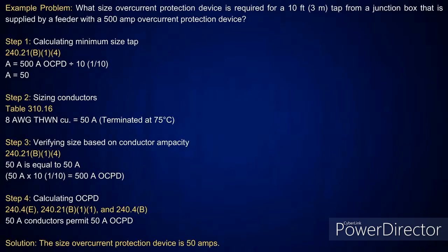Now, here's one. I'm doing a tap. Okay? So I'm going to ask you what size overcurrent device is required for a 10-foot tap from a junction box that is supplied by a feeder with a 500 amp overcurrent device that's upstream. I'm going to go 10%. Everybody remember what I've said on this. When you're doing taps, anything 10 foot or less, I divide by 10. Anything over that 10 foot, you take at a third. And if I did a tap with a transformer in the tap, you still do the primary at a third, but the secondary, you have to do it at a third with the ratio of the transformer.